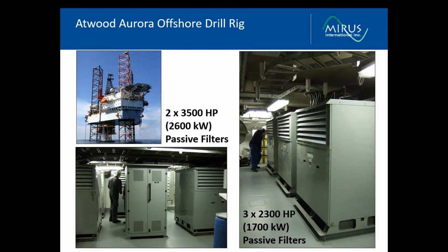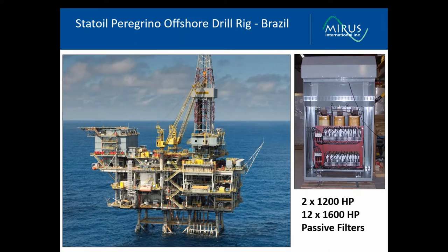This Statoil Peregrino site is a combined drill rig and production platform. Passive harmonic filters supplied with the drilling package work so well that they were kept connected during production operations, even when not drilling. This was because it made the underperforming phase-shifting transformer harmonic mitigation package provided with the production equipment operate within specifications. So not only did the harmonic filters meet the requirements of the certifying body while in drilling operation, it also provided harmonic mitigation for the production equipment.